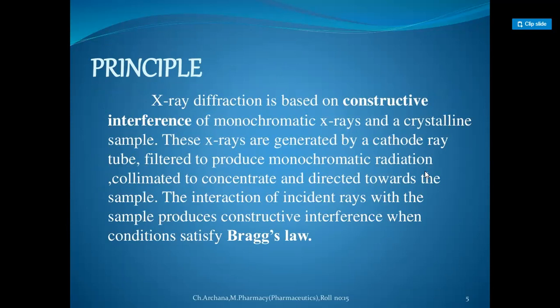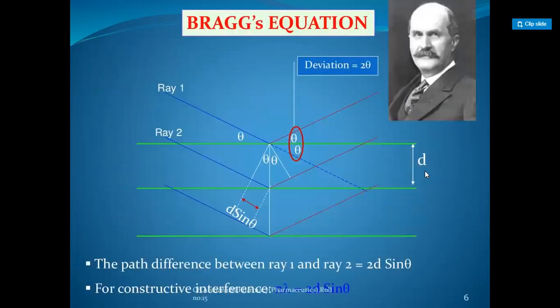The principle of X-ray diffraction is based on constructive interference of monochromatic X-rays and a crystalline sample. These X-rays are generated by a cathode ray tube, filtered to produce monochromatic radiation, collimated to concentrate, and directed towards the sample. The interaction of the incident rays with the sample produces constructive interference when conditions satisfy Bragg's law.